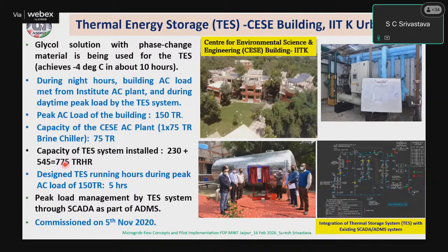That means if you have a load of 77 ton building load, it can run for 10 hours. The peak load is 150, which never comes. The average load is about 75, so up to 10 hours it can support with one charge. I don't think it has stopped - it has been continuously running since 2020 and has operated very satisfactorily.